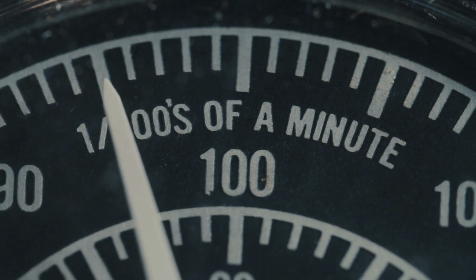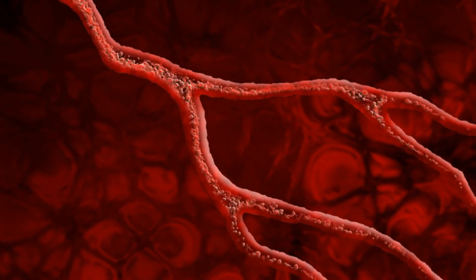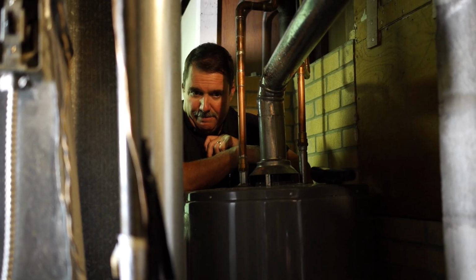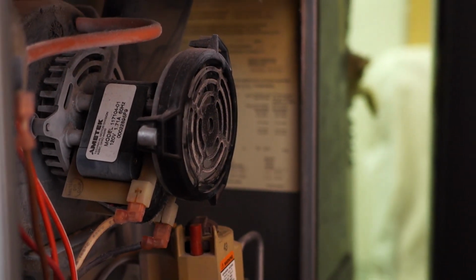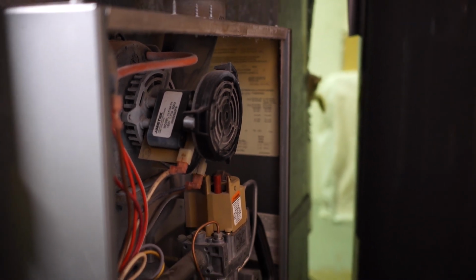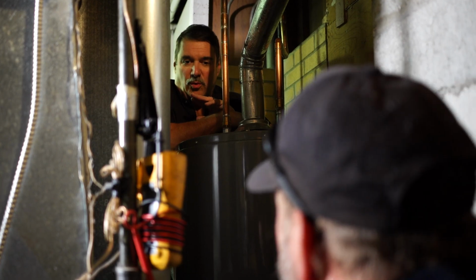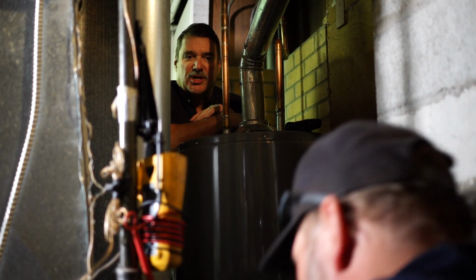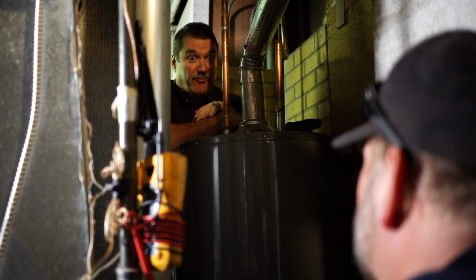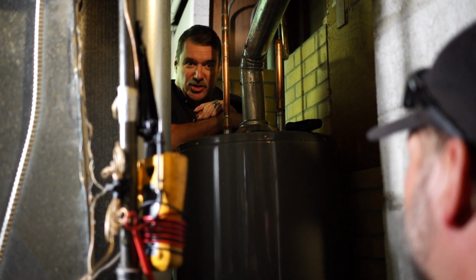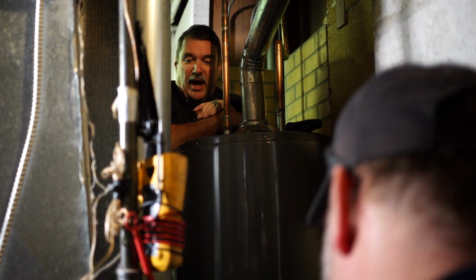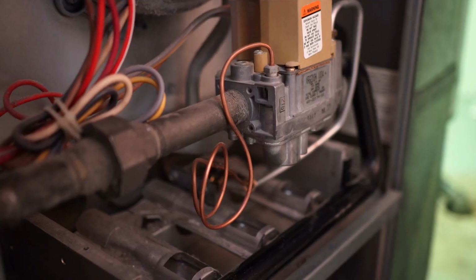That's sort of like our blood pressure—the older this thing gets, the more amps it takes to run. And like our blood pressure, the higher that gets, the more red line we're in. If I check on my clamp meter that I'm pulling 1.7 or even 2.0 amps, that's a big red flag that this inducer motor will need to be replaced. So we'd talk to the homeowner and suggest replacing it before winter, so they don't get that 2 o'clock in the morning call. That's why you do maintenance, to get these red flags out of the way.